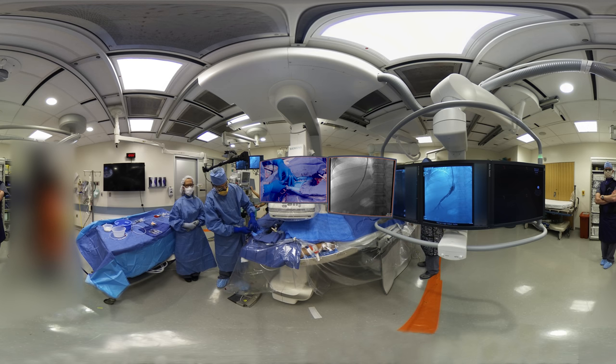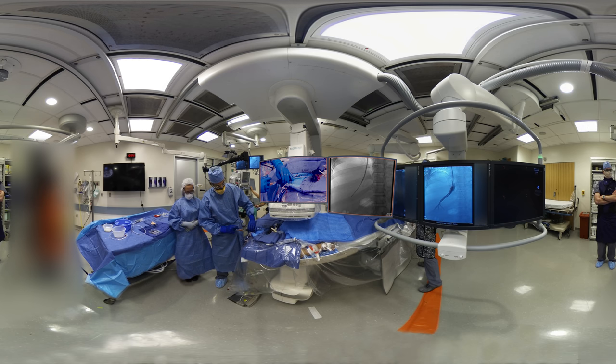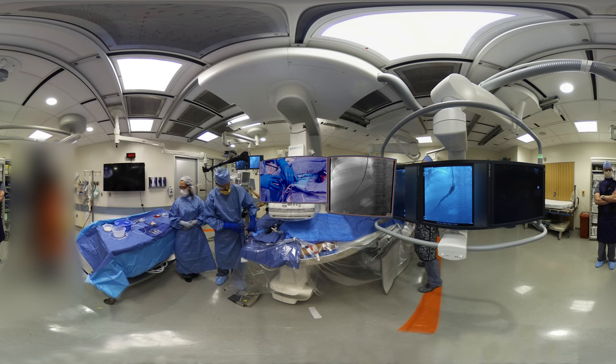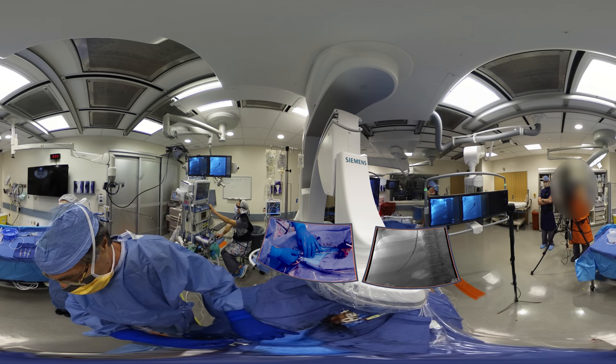I try to compartmentalize the tasks that each hand has and hand them back and forth. At this point I can control the entirety of the system with one hand, leaving me free to screw the syringe on or off the needle assembly without having it rotate and losing ground. That's essential in puncturing any small portal vein and in moving with the patient during respiration to keep the needle in place. So at this point we can bring the apparatus back and prepare for our puncture.